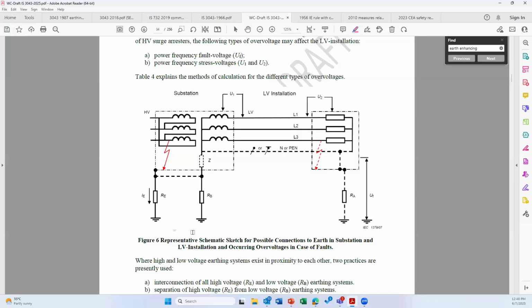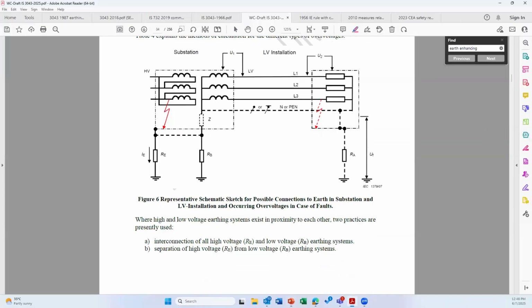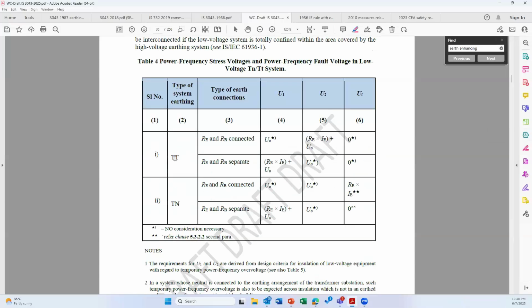On the screen, you can see the different misconceptions that we are having. You can see how the HV side fault is getting transferred to the LV side because of the HV side earth fault, and the ways to mitigate are also available there. On the LV side, you can go for either a TN or TT system. On the HV side, you can either separate or connect. The worst case scenario is when the equipment is connected. When the equipment is connected, if you have a TT system, then the potential rise will be high in your equipment. That is under column 5. Under column 5, there is a TT system, where the body and the neutral earth connection of the transformer are connected. This is the worst case scenario.